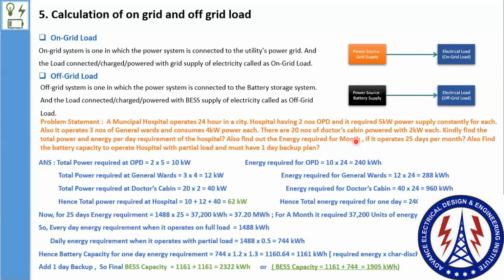Next, they asked us to find the battery capacity to operate the hospital with partial load and must have 1 day backup plan. Now it's time to brush up the brain. Daily energy requirement when it operates with partial load: when they say partial, if nothing is stated, consider it as 0.5 or 50%. So 1488 is my energy requirement, and with partial loading, the energy requirement would be 50% of it, for 1 day.